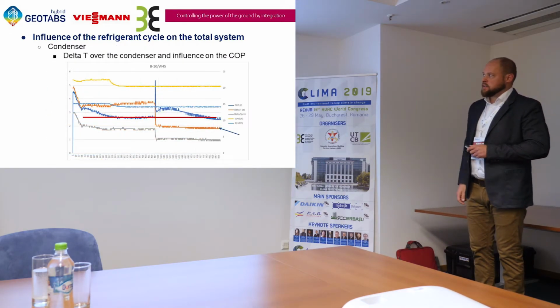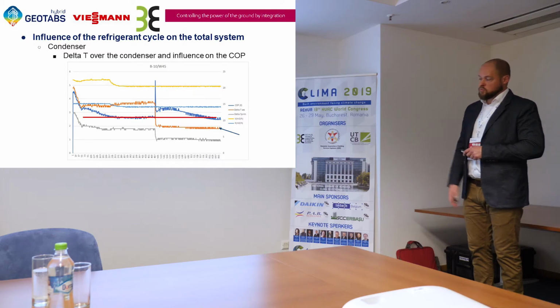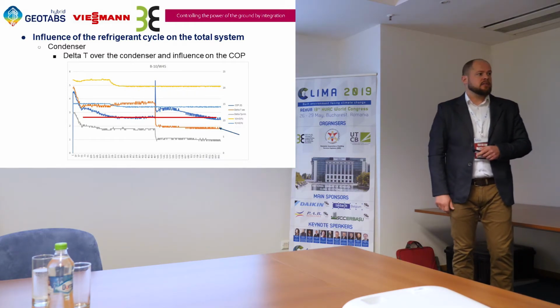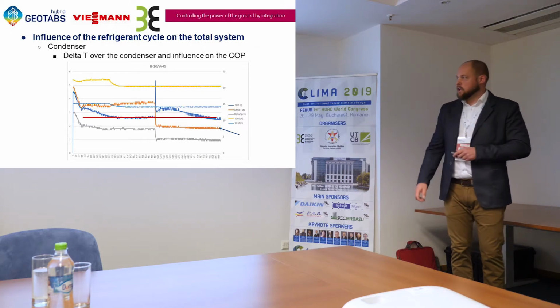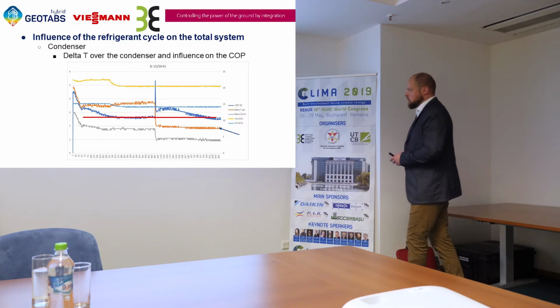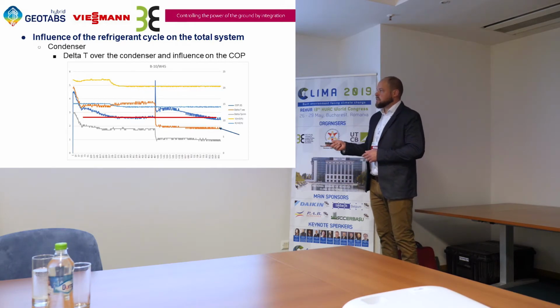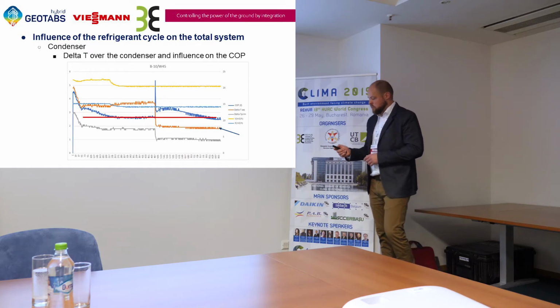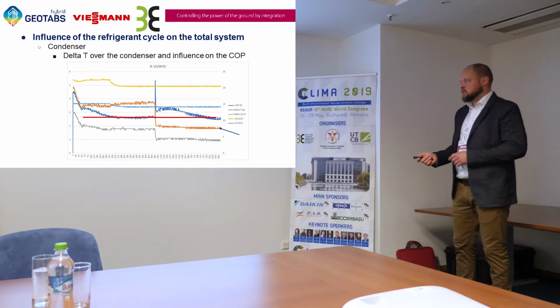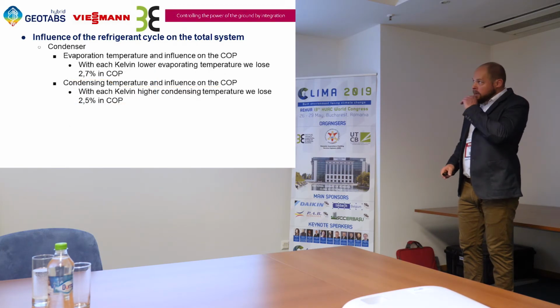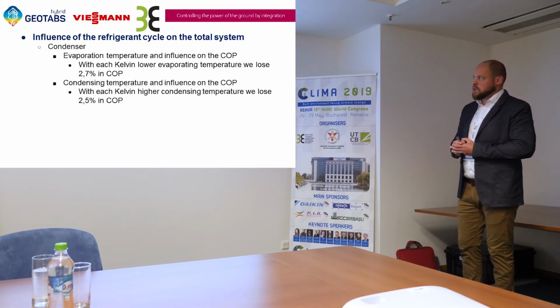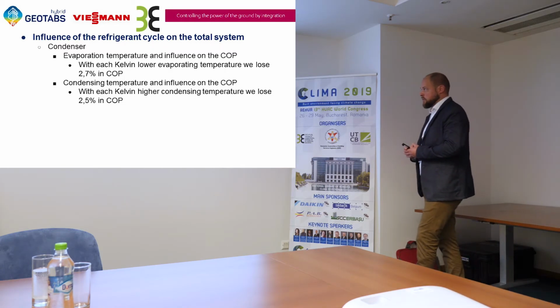What's the influence of the delta T? I didn't speak about that yet, because normally we use a delta T on the condenser side of about 5 degrees when we work with a buffer tank. When we make it bigger or smaller, you can see here, for example on 2 compressors, the condenser side and evaporating side, and then the delta T decreases because the volume flow is fixed. But a smaller delta T has the same effect on the COP as showed previously. So it stays about the same. What is really important is to keep the departing temperature of the heat pump as low as possible.